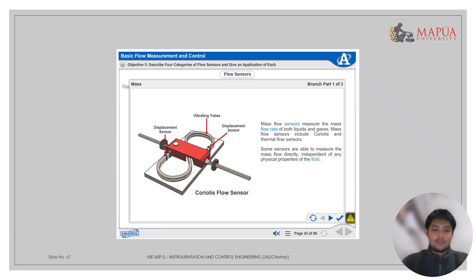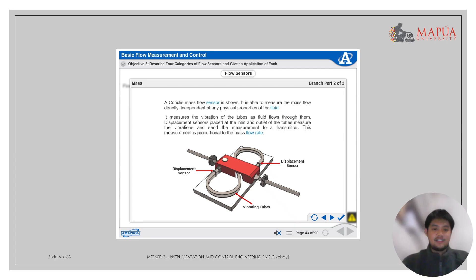A Coriolis mass flow sensor is shown. It is able to measure the mass flow directly, independent of any physical properties of the fluid. It measures the vibration of the tubes as fluid flows through them. Displacement sensors placed at the inlet and outlet of the tubes measure the vibrations and send the measurement to a transmitter. This measurement is proportional to the mass flow rate.